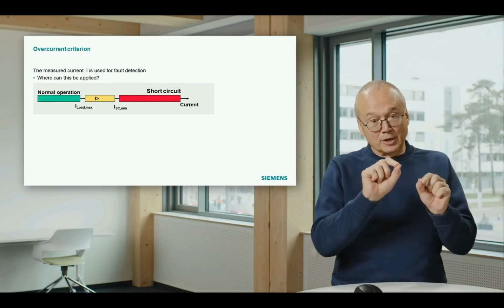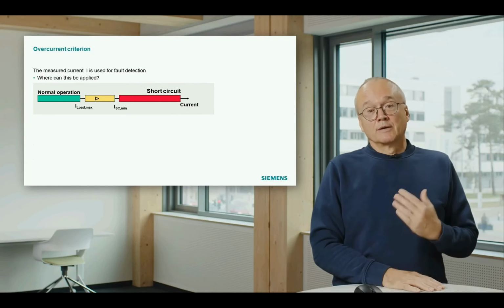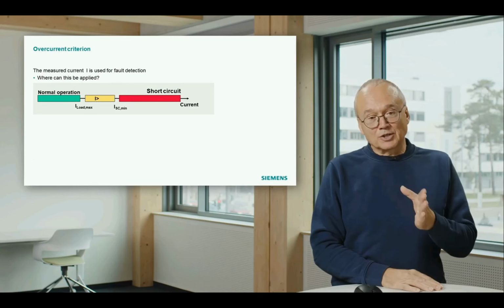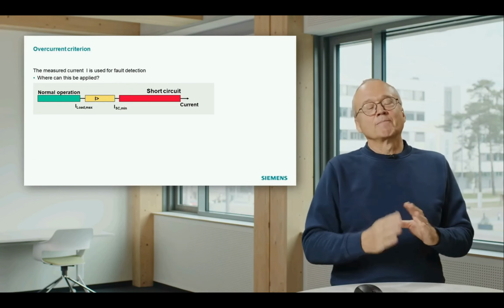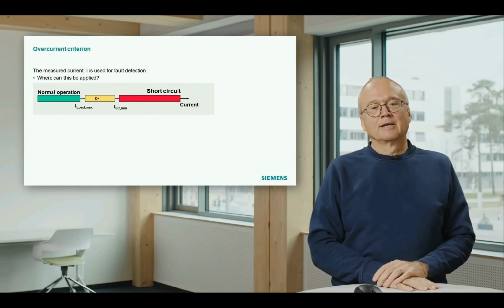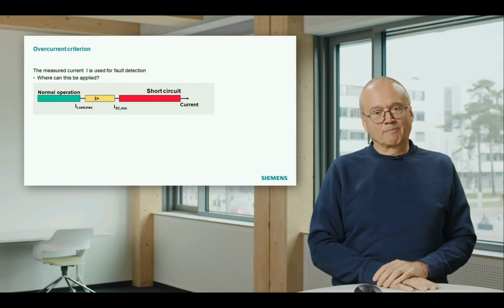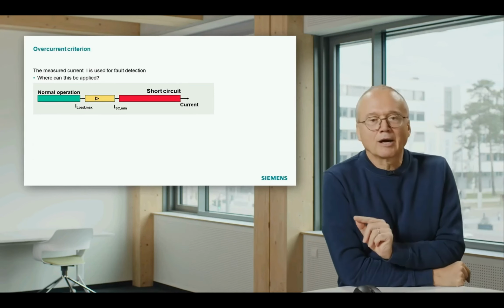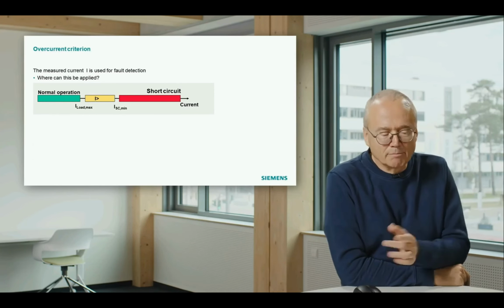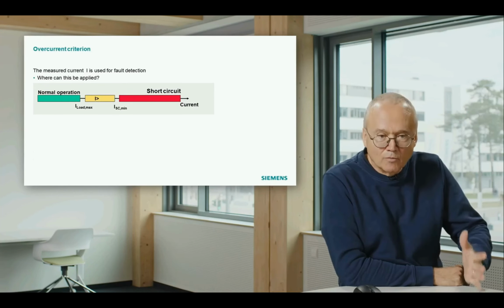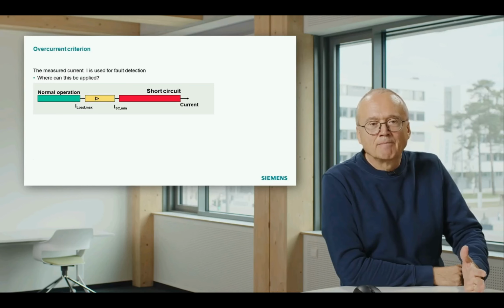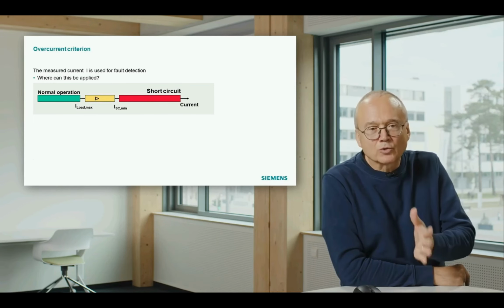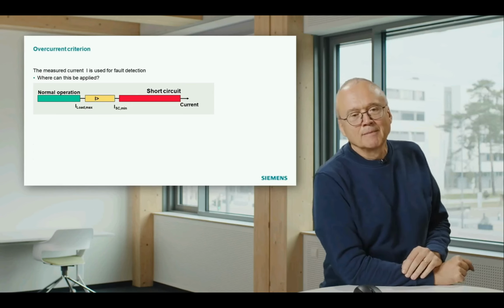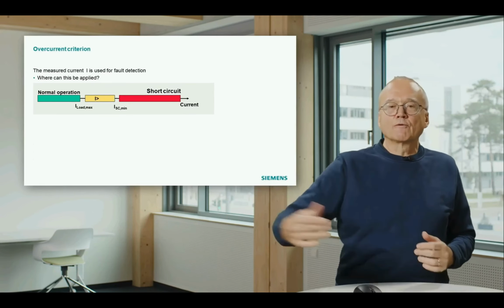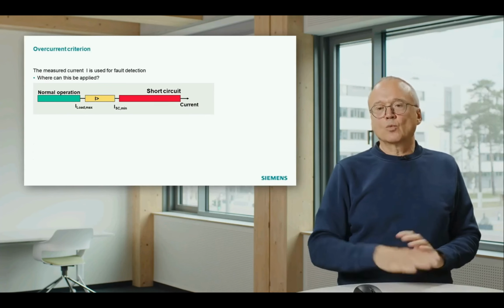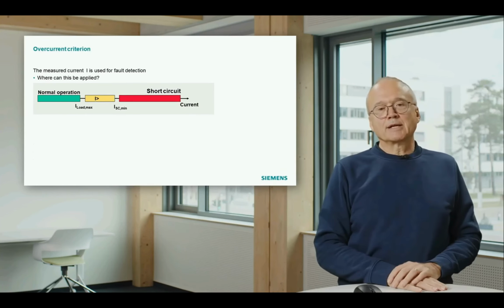And that means if you think about the maximum load current, you must take into account such considerations and must add a certain security margin there so that you don't get this problem. The other thing you also have to take into account is that you have to look into the future, because you calculate your setting when you install the device, but you don't want to reconsider the setting every month. That means you must have a setting which is also valid after some years, when maybe the system has been extended later on.